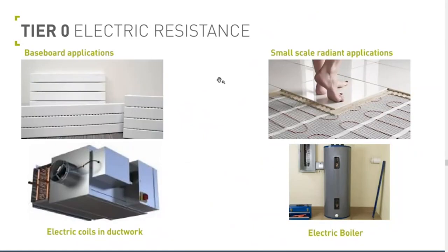Electric resistance generally has a negative connotation - think of it like a toaster coil with an airstream going through it. You're heating up copper wires or conduit really hot and blowing air past it. Same with an electric boiler - you're heating tightly wound coils with a lot of current going through them, and pushing water right past them. It's about 100%, or 99%, efficient, which sounds great, but in reality they use a ton of electricity, and electricity is expensive. There are other options that are a lot more efficient, which we'll talk about next.